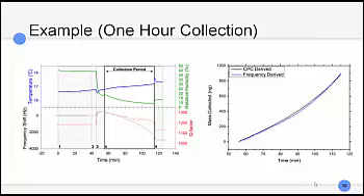So from the CPC derived, which I was just describing in black, and then we have the frequency derived in blue, which is taking this frequency shift and multiplying it by the theoretical sensitivity, which is on the order of about 28 hertz per nanogram. And so we get a decent correlation. You might be thinking this is a bit too good, and that is partially true. There's an additional scaling factor used, and for all the results I'll be showing that it ranges from about 5 to 10, and this is going to be accounting for those diffusion coagulation losses, and also some of the effects of the different types of aerosol as well.